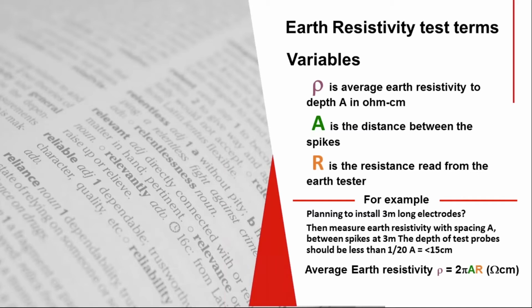We've discussed the parameters, so that's pretty obvious. Note the formula at the bottom: 2 pi A R. Resistivity is a volumetric measurement because current can spread out anywhere 360 degrees in the soil—it's not like wire gauge, which is constant. So instead it's a volumetric measurement, and the units of resistivity are typically ohm-centimeters. You can use ohm-inches or ohm-feet if more convenient, but the industry standard is ohm-centimeters.